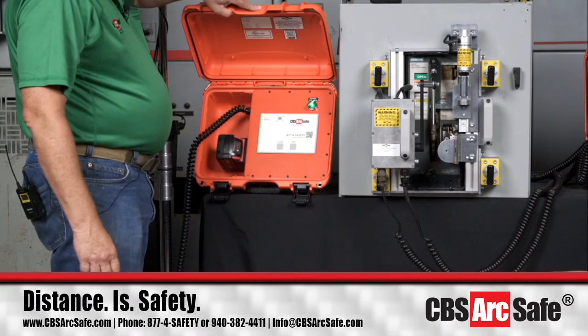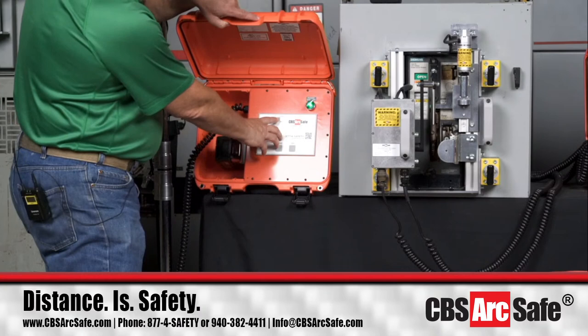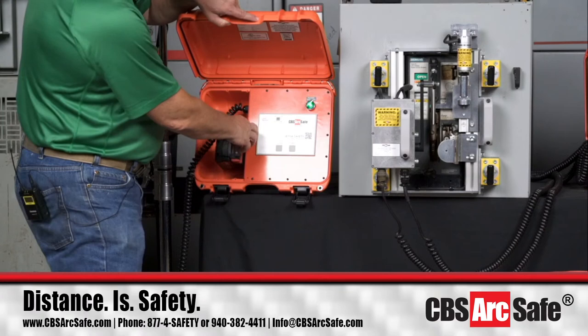Okay, and Brian, I just want you to be close in here. We've got our AR function. AR is what's called automatic return, and we had to have that for various actuators. If we want to move this around, we just move this to the appropriate thing. If we want it to open or operate for just the close, then we put it in the close and we hold it down for 5 seconds, the light will turn green. And now it's going to be in that position, okay?